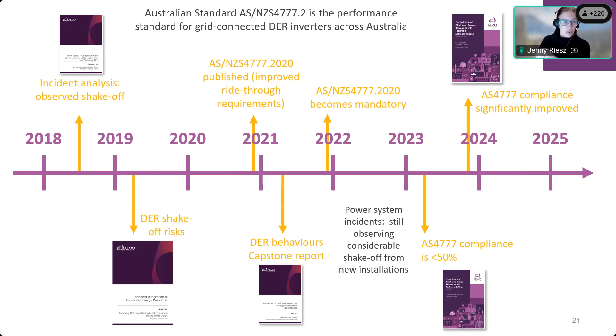But what I want to emphasize here is the timeline for rectifying these issues. This was first noticed around 2017, 2018, and it's really only around 2024, 2025 that I'd suggest we've actually got measures in place addressing it successfully, now seeing growing levels of inverters connected that will ride through. So for these sorts of issues, dealing with distributed resources and customer devices spread across the grid, we need to allow for really long lead times to address them.